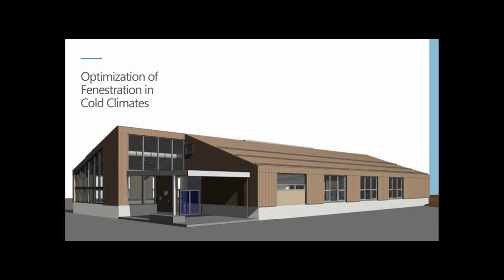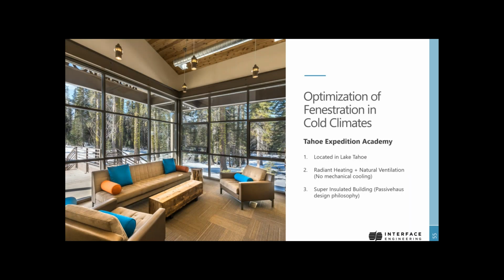The final section of this presentation is cold climate fenestration optimization, for a project in South Lake Tahoe. It's an office and admin building using radiant heating but no mechanical cooling, which is important for how the facade relates to total energy consumption. We used passive house design philosophy here because it's a very cold climate, so we super-insulated the building and targeted very low infiltration rates.